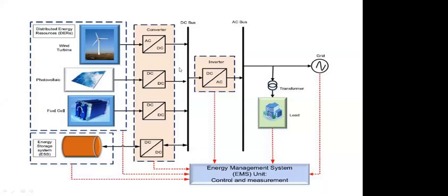In other cases, each source or device may have its own inverter connected to the common coupling point. The difference is: with a single inverter, if there's any problem in it, the whole microgrid or all sources have to be disconnected. With a separate inverter for each device, if a problem occurs in a particular source, only that inverter has to be shut down. So again, it's an economic and operational issue depending on the configuration.